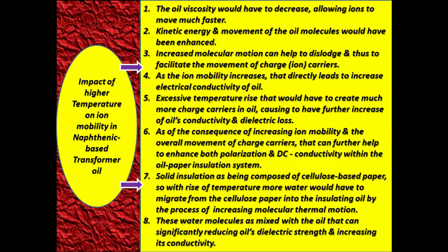Solid insulation is composed of cellulose based paper, so with the rise of temperature, more water migrates from the cellulosic paper into the insulating oil by the process of increasing molecular thermal motion. These water molecules, as mixed with the oil, can significantly reduce the oil's dielectric strength and increase its conductivity.